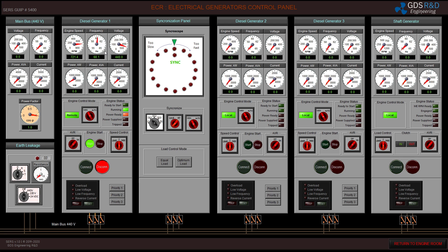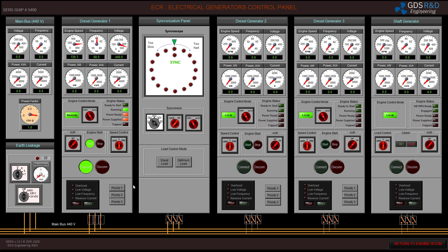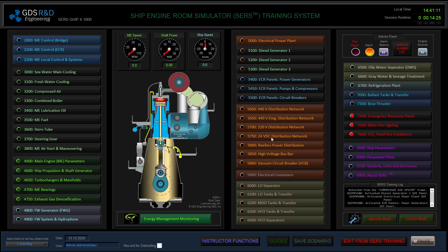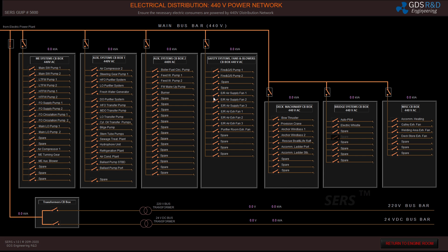It looks good right now. There is no trip on the control panel and I am ready to connect my diesel generator to the bus bar. I now have 440 volts on my main bus bar. I will go check the distribution network — the main bus bar is energized, as I can tell by the color.